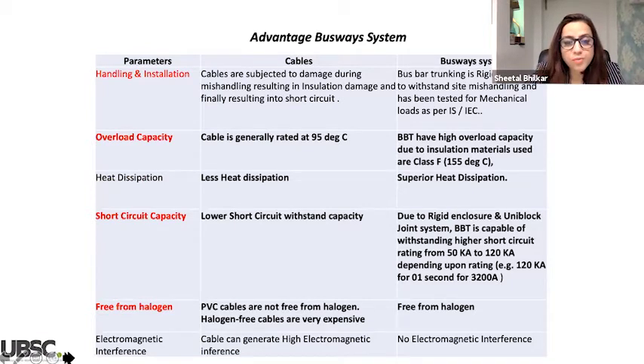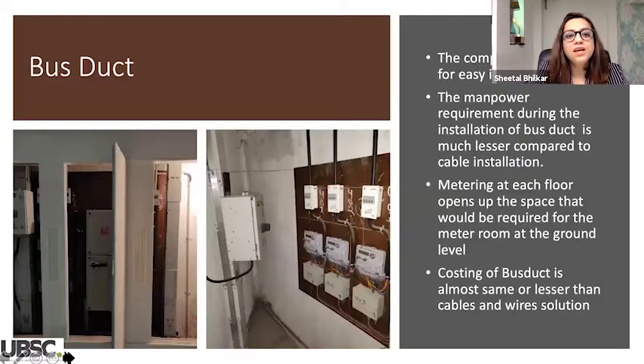So in all our projects, wherever we are designing high rises, we are recommending bus ducts, and supply companies also nowadays are giving permission. Even MSEDCL, now they have started giving permission for rising mains. Otherwise we used to face this problem with projects in Thane, where we were not getting permissions for bus duct, but nowadays they are also giving permission for bus duct. So we are widely using this solution for high rises.